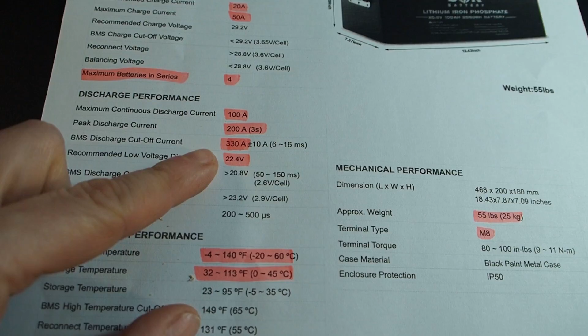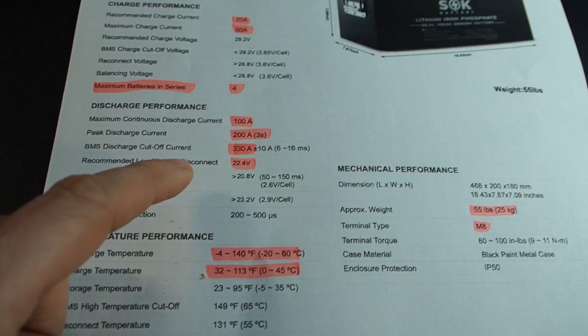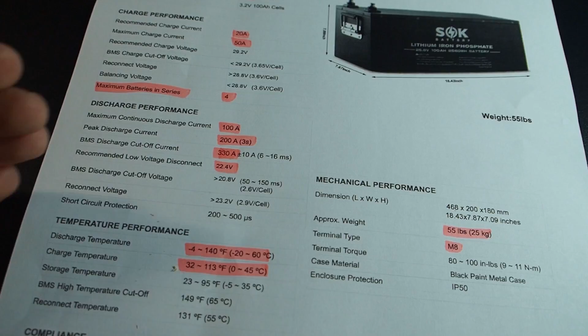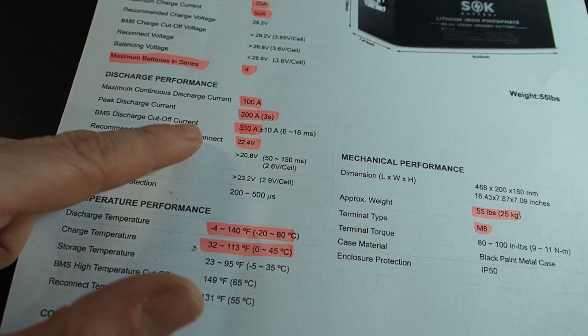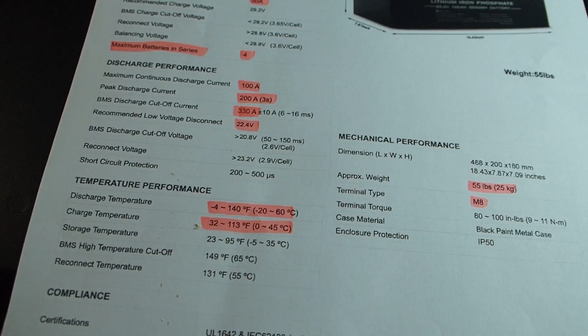Next, here we can see that you can discharge the battery with 100 amps. That's pretty powerful. And for peaks, it can for a short time do more than this, 200 amps. But then the BMS will cut off the current at 330 amps after 6 to 16 milliseconds.